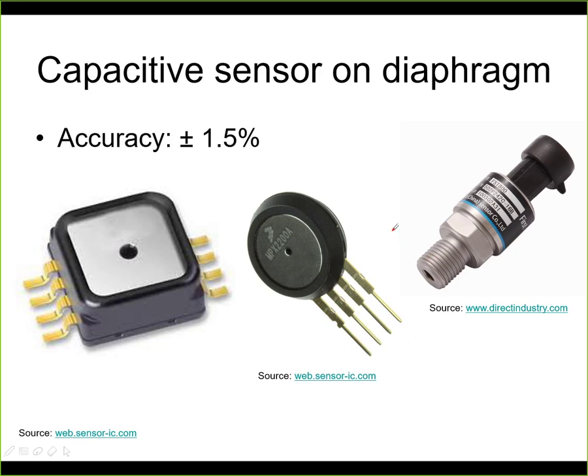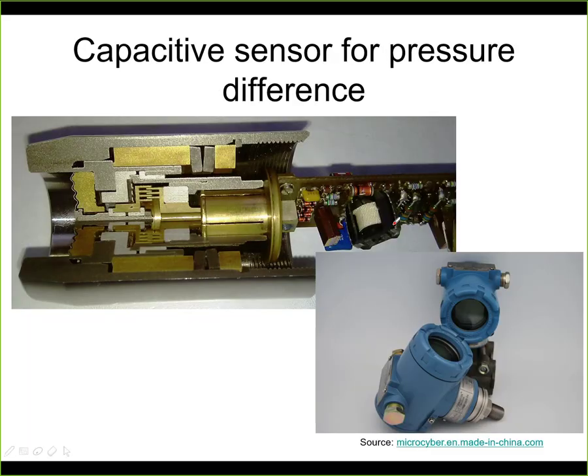Typically the accuracy is about 1, maybe 1.5%. So it's about the same accuracy as the Bourdon tube, but in this case we have an electrical output. Now what you see here are the insides of such a smart sensor. So the sensor looks like this. They have a typical shape, so this is the input port.